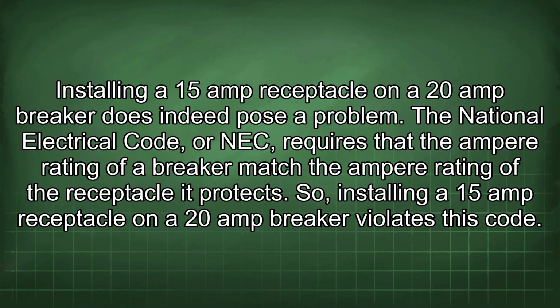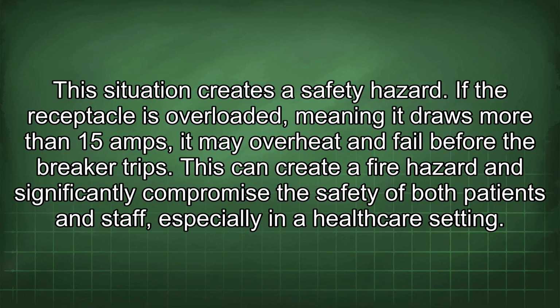Installing a 15-amp receptacle on a 20-amp breaker does indeed pose a problem. The National Electrical Code, or NEC, requires that the ampere rating of a breaker match the ampere rating of the receptacle it protects. So, installing a 15-amp receptacle on a 20-amp breaker violates this code. This situation creates a safety hazard.